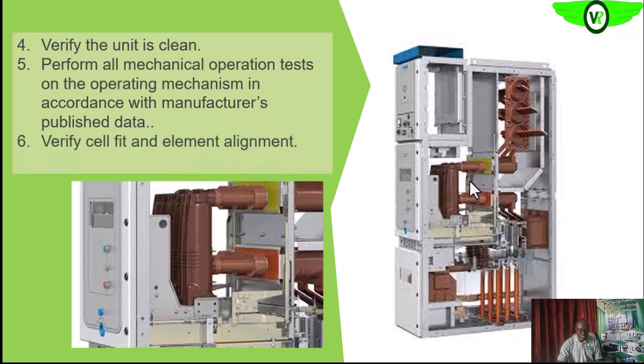As we said earlier, we want to see that the breaker is properly aligned with the cell, with a proper cell fit. We also want to look at the racking mechanism, that the breaker will freely rack into the switchgear.